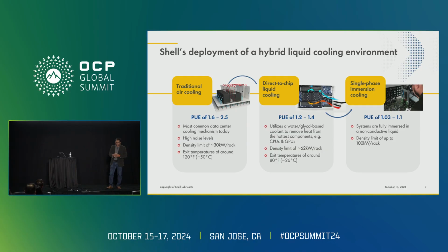In 2021, we started with direct-to-chip cooling. We brought down the PUE from 1.6 to 1.2. That's also a representation of how much change we can bring to our own needs. One highlight: 30 kilowatts per rack was probably the limitation we had with air cooling. We scaled it, doubled it to close to 70 kilowatts with CoolIT systems running DLC there.